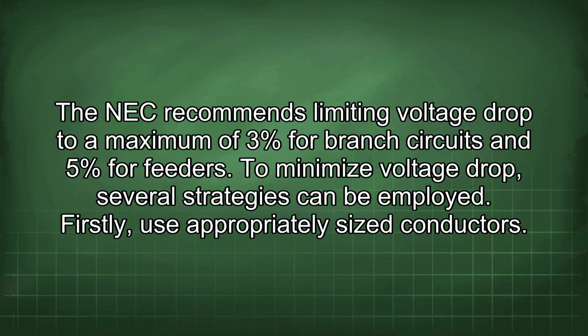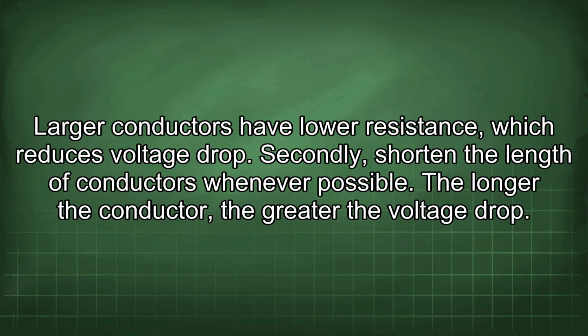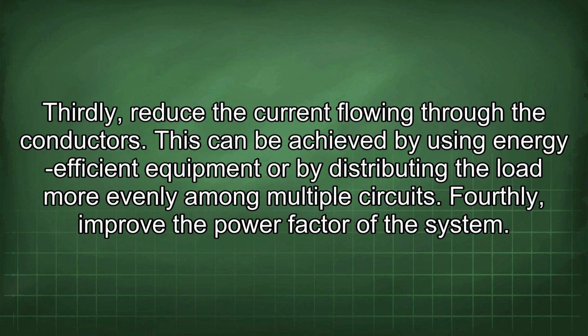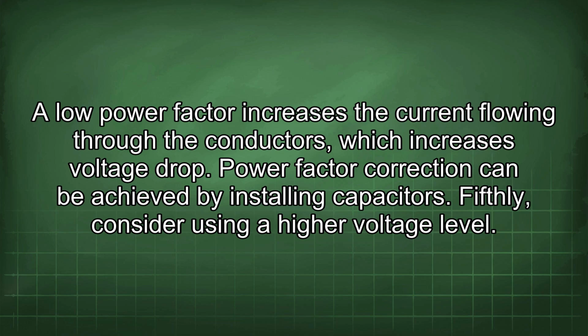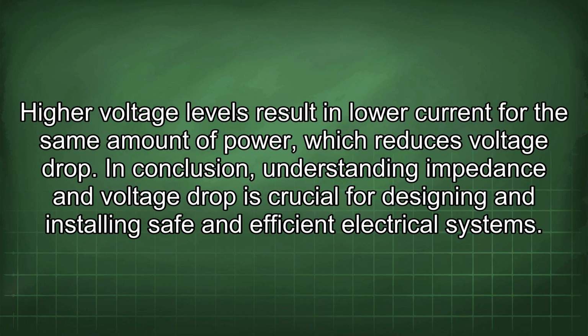To minimize voltage drop, several strategies can be employed. Firstly, use appropriately sized conductors. Larger conductors have lower resistance, which reduces voltage drop. Secondly, shorten the length of conductors whenever possible. The longer the conductor, the greater the voltage drop. Thirdly, reduce the current flowing through the conductors. This can be achieved by using energy-efficient equipment or by distributing the load more evenly among multiple circuits. Fourthly, improve the power factor of the system. A low power factor increases the current flowing through the conductors, which increases voltage drop. Power factor correction can be achieved by installing capacitors. Fifthly, consider using a higher voltage level. Higher voltage levels result in lower current for the same amount of power, which reduces voltage drop.